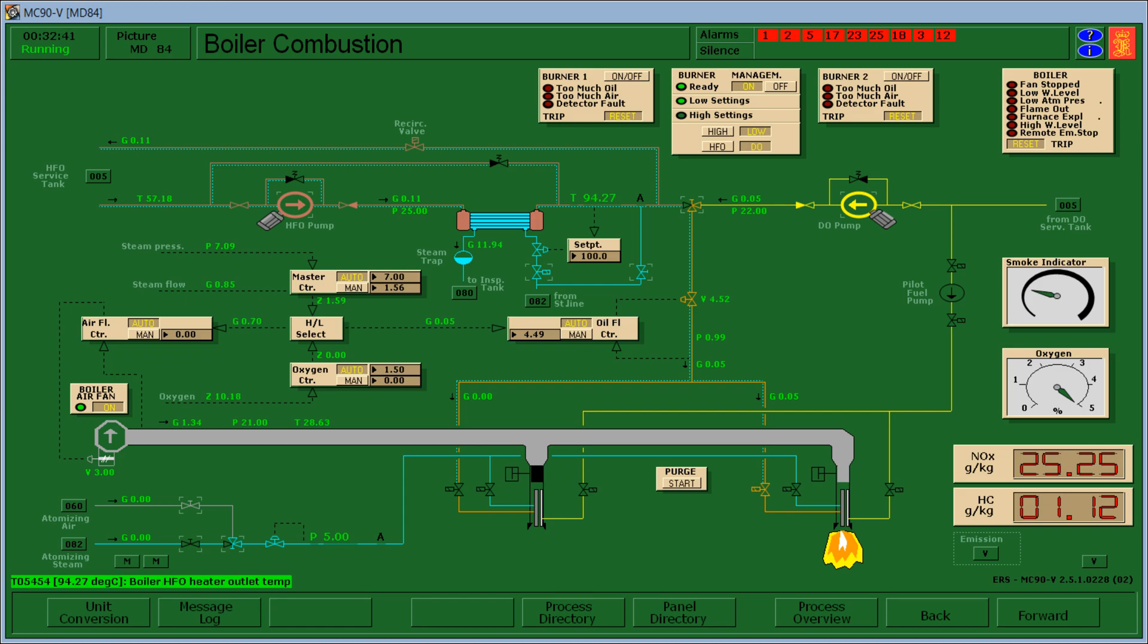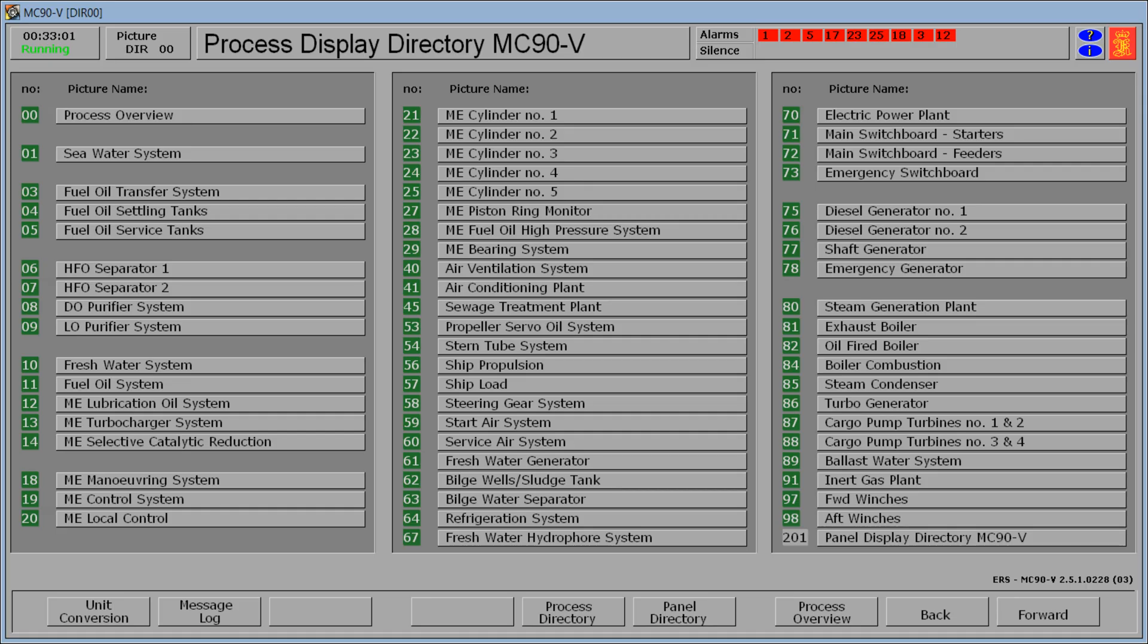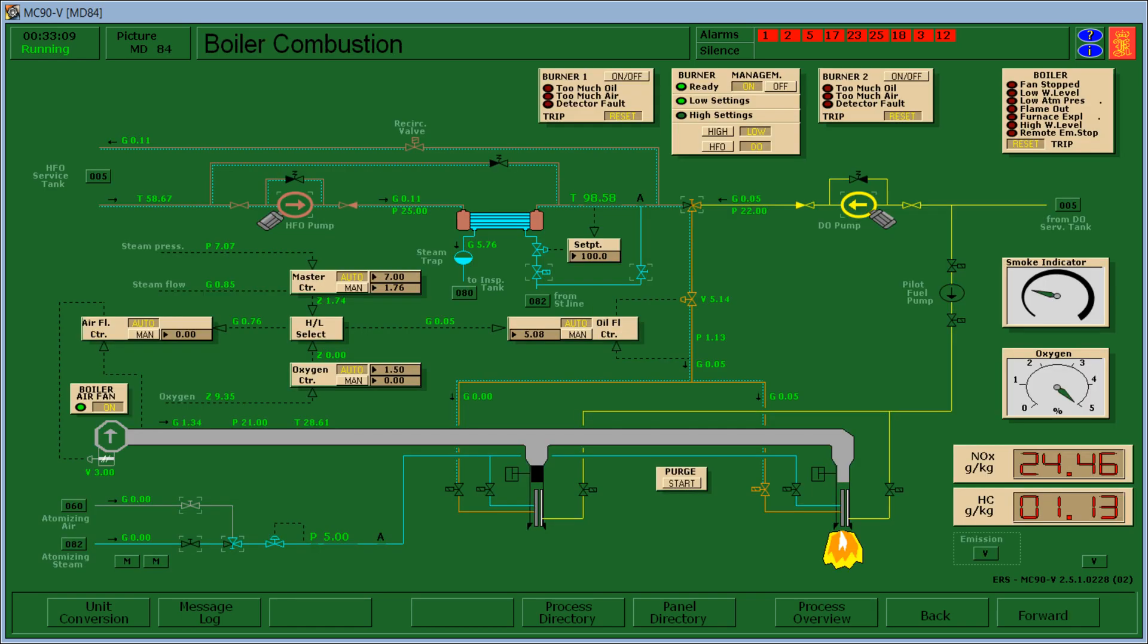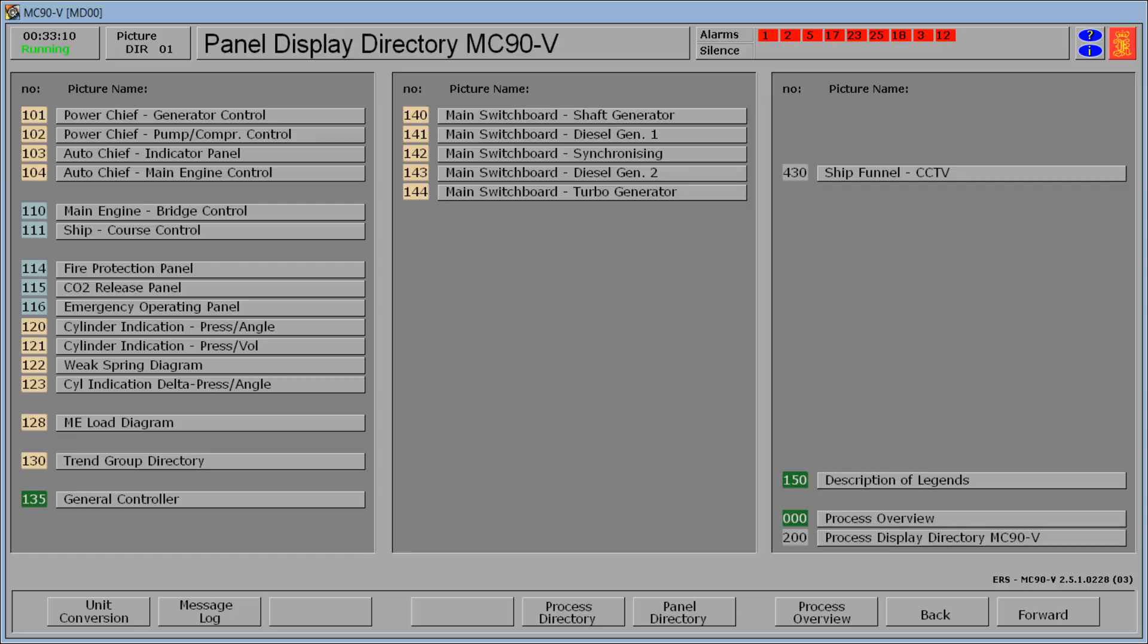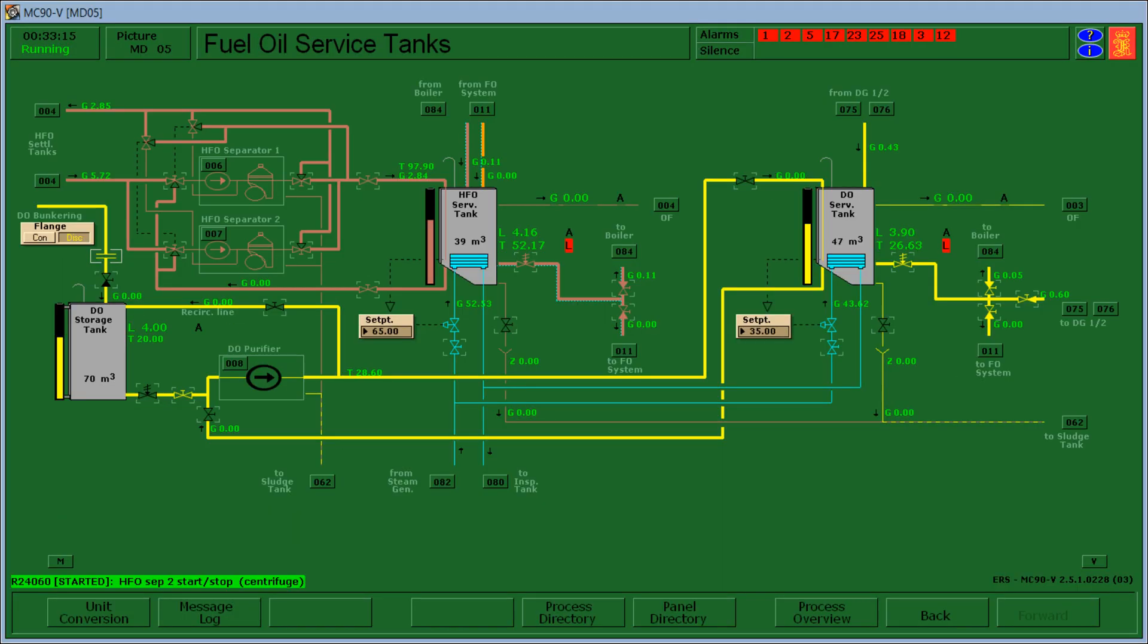Now when it reaches the set point let's switch the heavy fuel oil here. Then I'll show you that I have prepared my HFO separator or the purifiers. Then here I open the service tank heating shut off valve. So it helps the temperature of the heavy fuel oil to increase too.